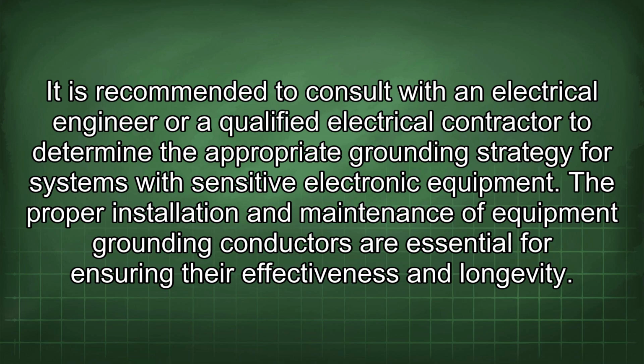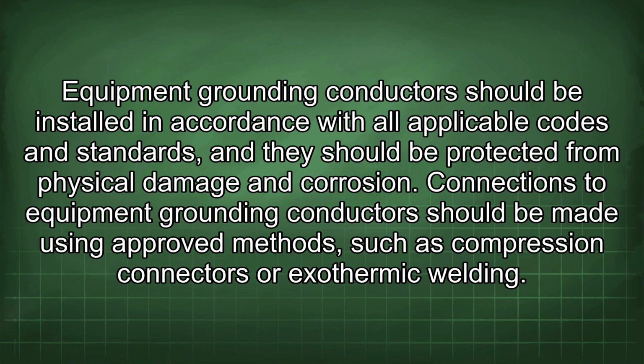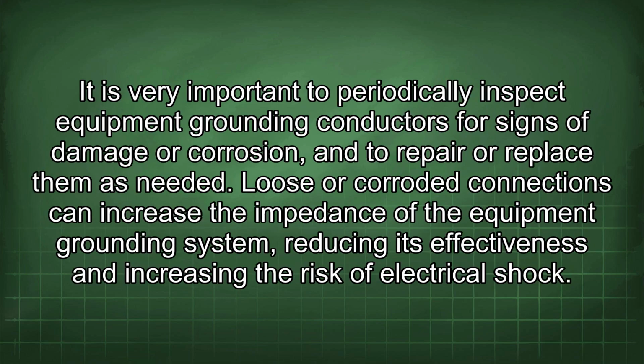The proper installation and maintenance of equipment grounding conductors are essential for ensuring their effectiveness and longevity. Equipment grounding conductors should be installed in accordance with all applicable codes and standards, and they should be protected from physical damage and corrosion. Connections to equipment grounding conductors should be made using approved methods such as compression connectors or exothermic welding. It is very important to periodically inspect equipment grounding conductors for signs of damage or corrosion and to repair or replace them as needed.